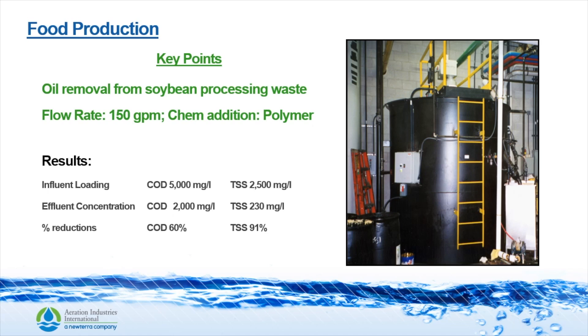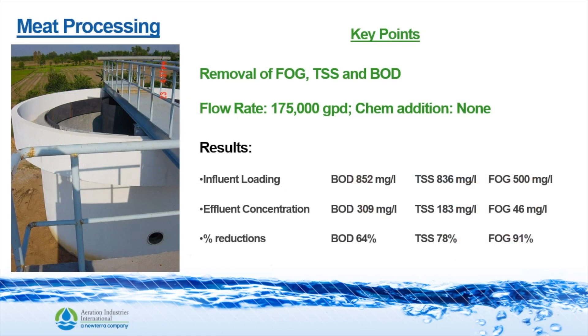This yielded a COD removal rate of 60% and a TSS removal rate of 91%. Here is a meat processing plant where they were removing FOG, TSS, and BOD. It was a 175,000 gallons per day plant and they added no chemicals. The influent BOD was 852 mg/L, TSS was 836 mg/L, and FOG was 500 mg/L. The effluent concentrations were 309 mg/L BOD, 183 mg/L TSS, and 46 mg/L FOG — yielding 64% removal of BOD, 78% removal of TSS, and 91% removal of FOG.